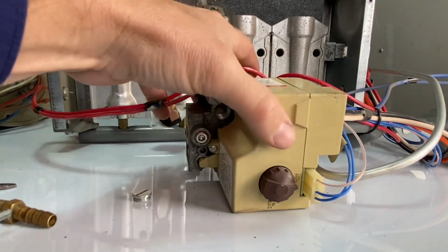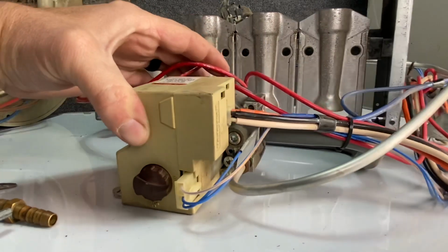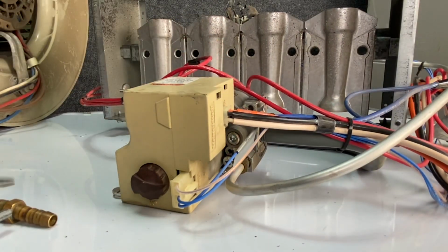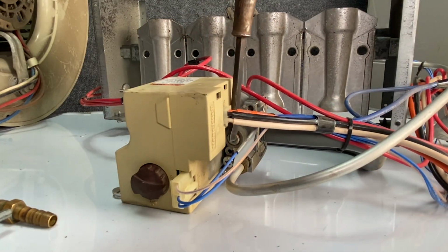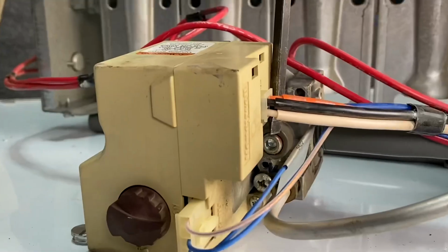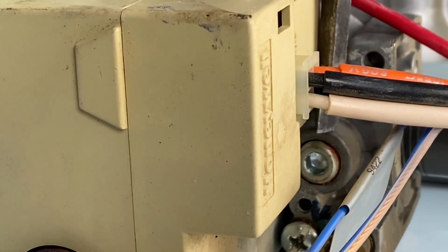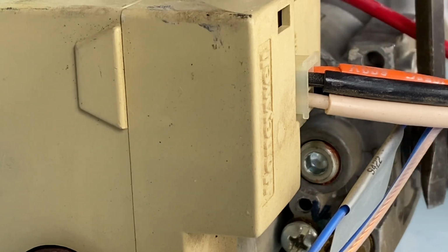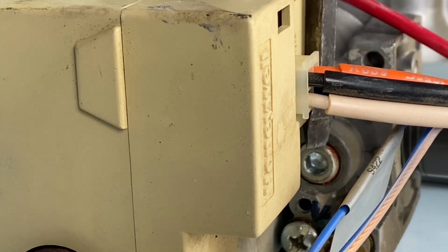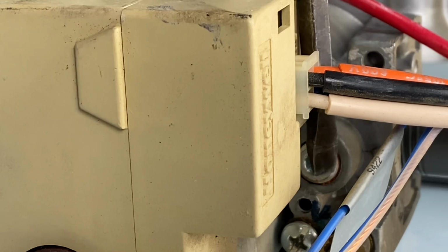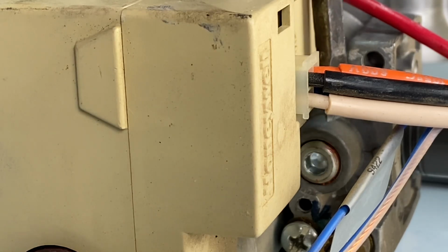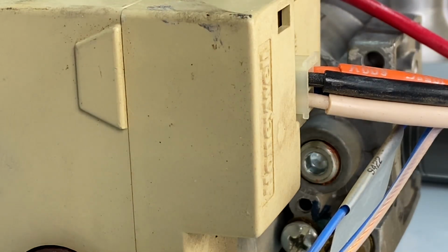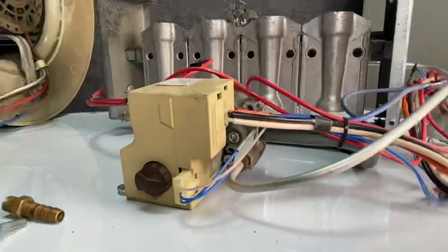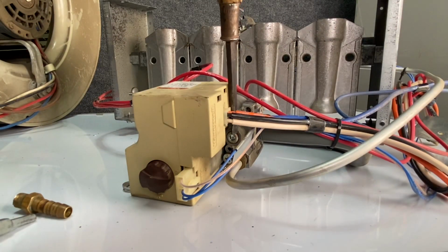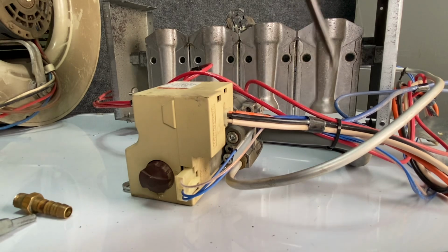On the other side is where we see our output port. This port right here is very similar to what we saw earlier. This port is going to be the manifold pressure, so the manifold is coming out on this side. We would unscrew that with the same exact tool. We'd put the same adapter in there, and this way when the combination gas valve opened, we would see what the pressure was in the manifold. So this port is giving us the same pressure that's in this manifold.